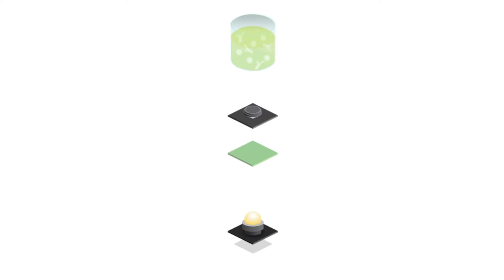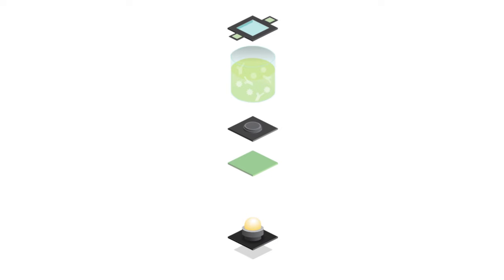A spectrophotometer is an instrument used to measure the intensity of light at a particular wavelength in the visible spectrum. This type of instrument can be used in the clinical laboratory to determine the concentration of a substance in solution by measuring the amount of light either transmitted or absorbed when a beam of light is passed through a sample reaction at a specific wavelength.